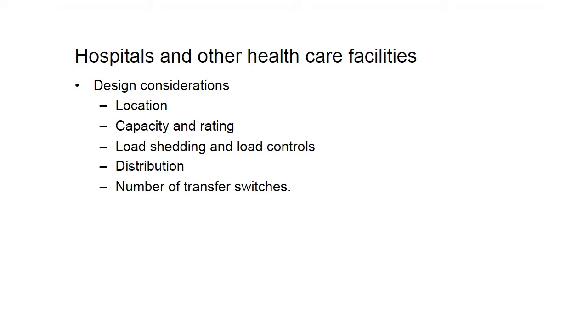And we'll touch on that a little bit here in a couple more slides as to common ways of handling that. From a distribution standpoint, I mentioned earlier, you want to have multiple paths. Again, physical separation is a great thing to help support and ensure some sort of longevity and robustness in the system. And then the last area I want to touch briefly on is transfer switches. The number of transfer switches that you'd have in your system is going to be impacted by the amount of load, the type of loads that you're serving, and the arrangement or the dispersement across your facility. Generally, there's three types of transfer switches. You've got your automatic, your manual, and delayed.